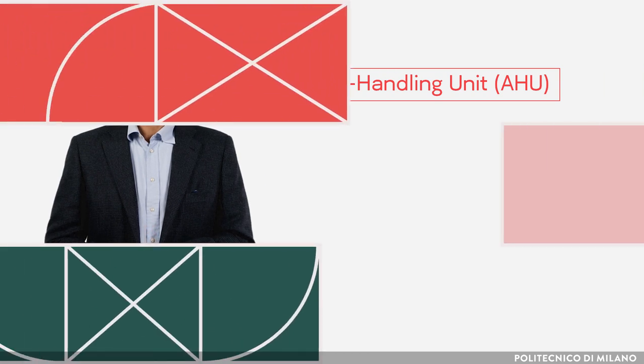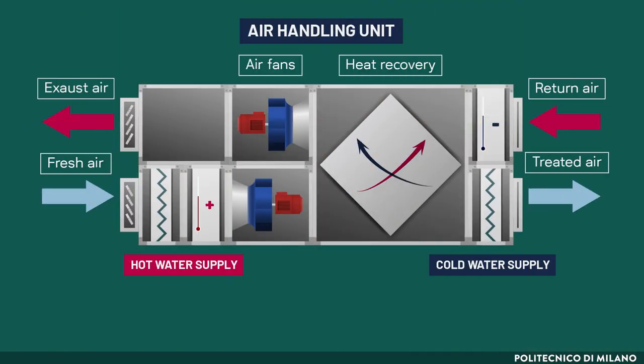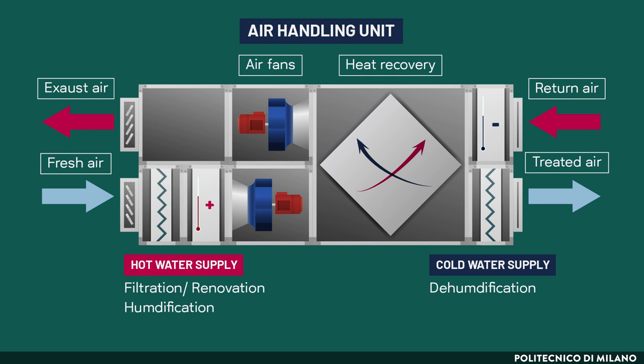In the case of all-air or air-water systems, the generation subsystem includes the air handling unit. The air handling unit manages a series of operations upon the air before it is distributed: filtration, renovation, humidification and dehumidification, heating, cooling, and heat recovery. To pursue these tasks, it requires hot or cold water or, alternatively, a refrigerant coming from the generation subsystem.